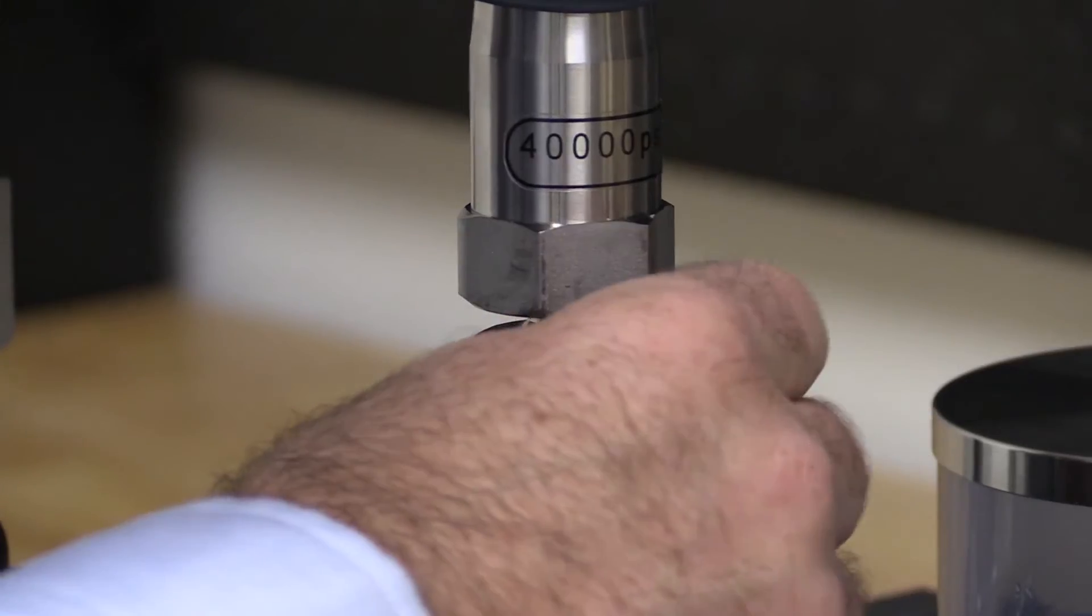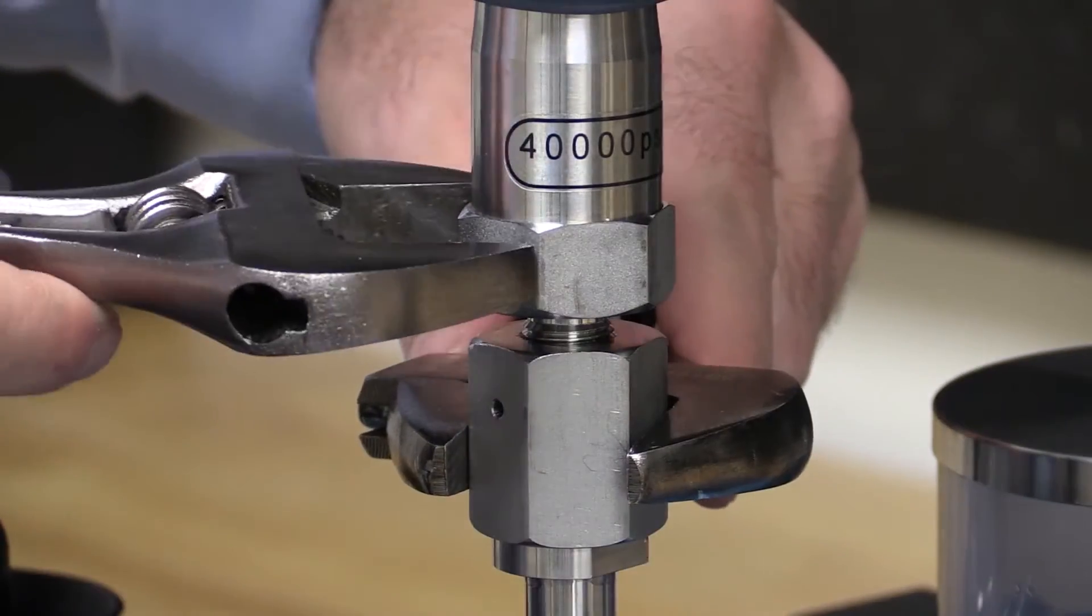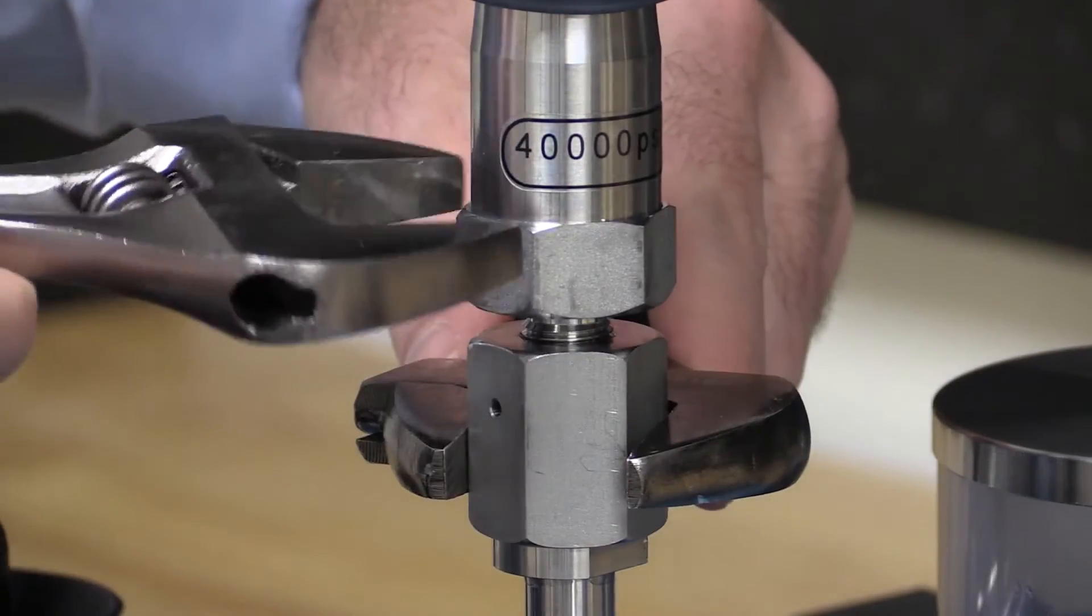The first step is to securely connect the reference to the pump. The device under test, or DUT, could also be connected, but only if it is okay for the DUT to have a vacuum pulled on it.